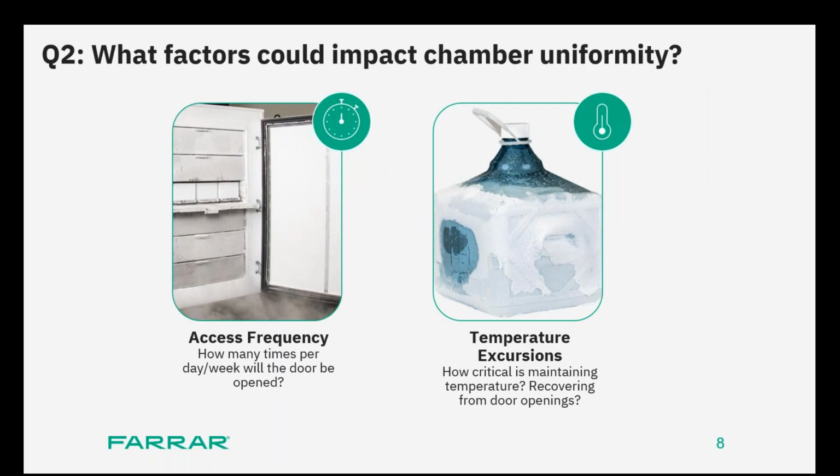Thank you again, Rebecca. Excellent question. So when it comes to temperature or chamber uniformity, and we're going to use these two terms interchangeably because they refer to the same concept, what's really important to determine is whether your materials or samples are being stored for long or short-term storage, because that would be directly correlated to high or low frequency of door openings, right? And as the old proverb goes, all roads lead to Rome, meaning that at the end of the day, what you're trying to do is look at the end goal of minimizing and mitigating temperature excursion, right?